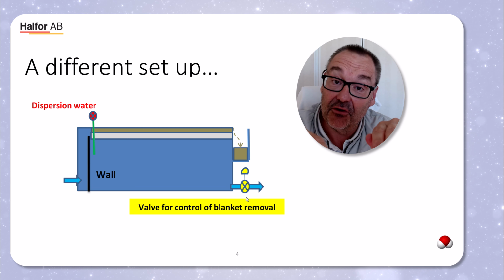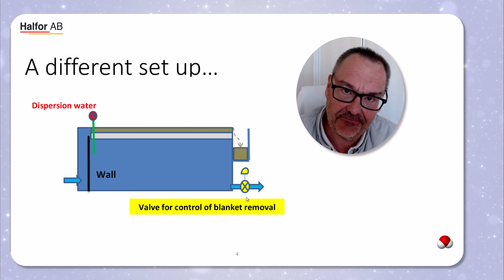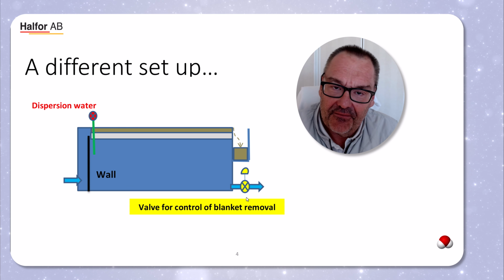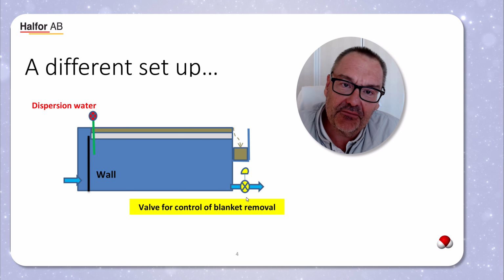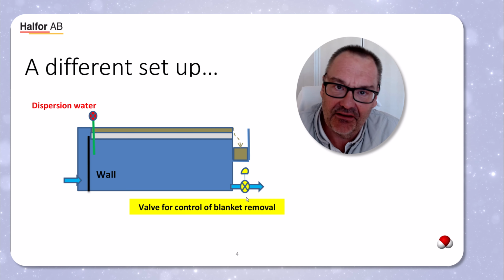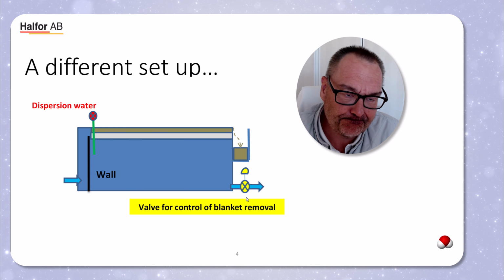Then the valve opened and operation continued as normal. When this was implemented, it was possible to increase the loading by 20%, which is quite good.